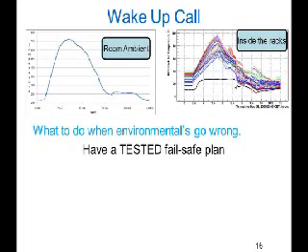We had a very serious wake-up call. We had a power failure in the cooling system, but not in the computer room. So things got very hot very quickly. In the infrastructure room, temperatures were rising about one degree centigrade per minute. The idea is when you have a problem like that, you have a tested fail-safe plan. Clearly we didn't — we dropped the ball when everybody thought somebody else had done it. The monitoring worked perfectly: it was getting hot, it was getting real hot, it was awfully hot. And nobody noticed for about an hour.